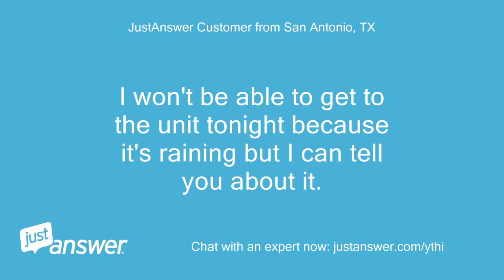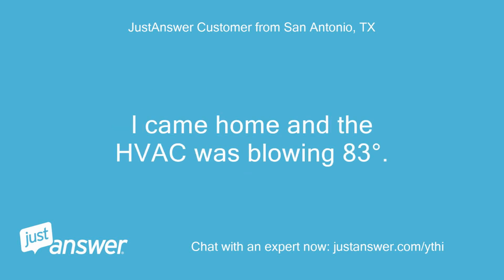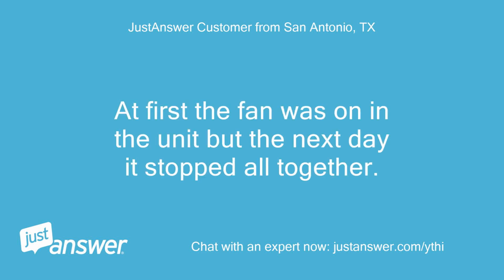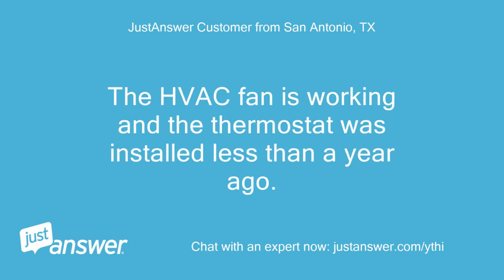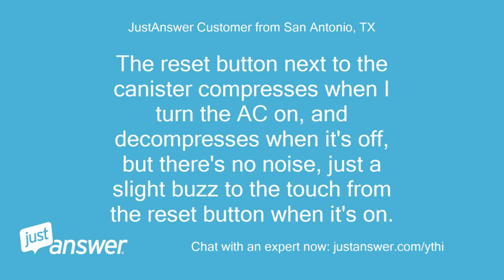I won't be able to get to the unit tonight because it's raining, but I can tell you about it. I came home and the HVAC was blowing 83 degrees. At first the fan was on in the unit, but the next day it stopped altogether. The HVAC fan is working and the thermostat was installed less than a year ago. The reset button next to the canister compresses when I turn the AC on, and decompresses when it's off, but there's no noise, just a slight buzz to the touch from the reset button when it's on.